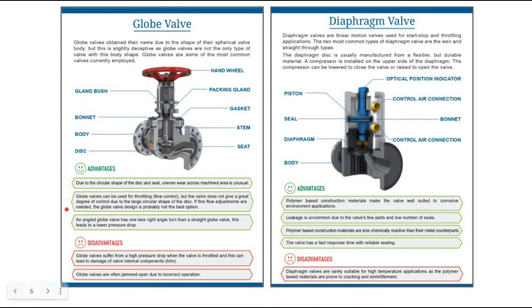Globe valves can be used for throttling as well, but the valve does not give a great degree of control due to the large circular shape of the disc. If fine flow adjustments are needed, the globe valve design is probably not the best option. An angled globe valve has one less right angle turn than a straight globe valve, which leads to a lower pressure drop, giving the angled globe valve a slight advantage over the straight globe valve.